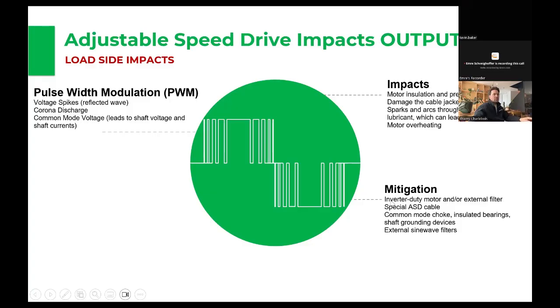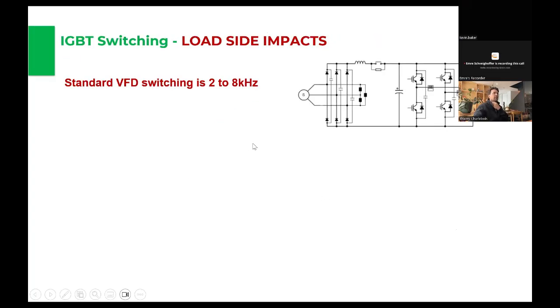How do you mitigate that? Well, you've got to pay extra for inverter duty motors, which can handle the spikes. Special VFD duty cable. You can still use shielded cable, but really what you're after is the insulation of the cable to be able to withstand these voltage spikes as well, and the corona discharge. You can introduce common mode chokes or insulated bearing shaft grounds, like we mentioned before, and then external sine wave filters. And again, with the external sine wave filters, we'll talk about that in just a second.